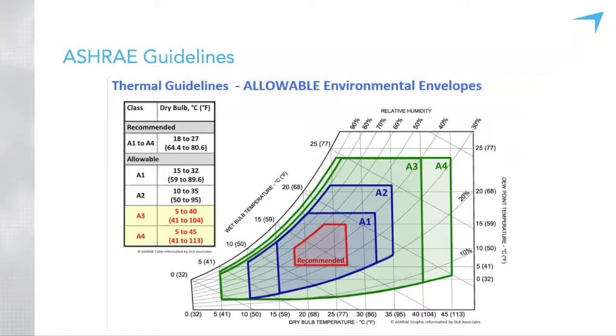If you look at that range, it's fairly wide. In my own data center and several others I've visited, I don't always see temperatures at 59, but I'll see temperatures in the 66 to no more than 70 range. Looking at a class A1 server, you can go up to at least 90 degrees and still have the least amount of risk of failure to your equipment.